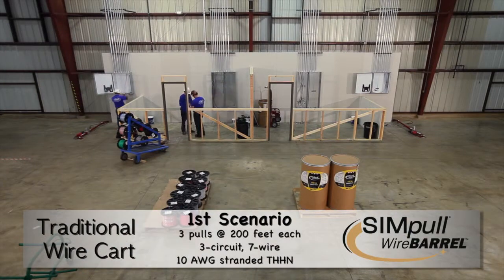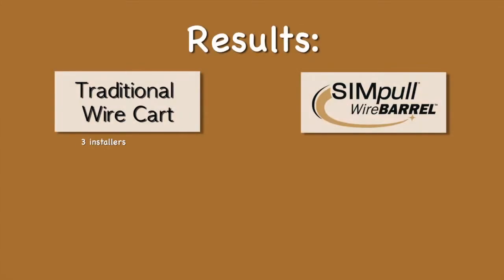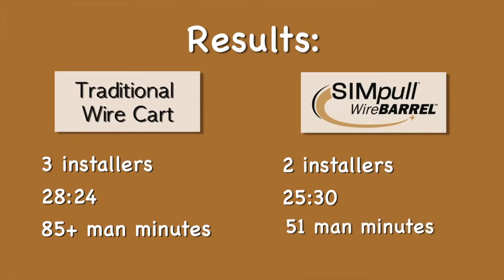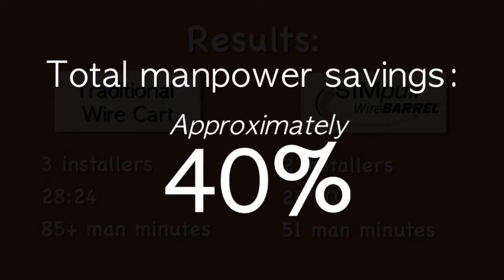Like these 30-inch doorways, allowing the wire to be located closer to the feed conduit. In this scenario, three installers using the traditional wire cart method completed their pulls in 28 minutes and 24 seconds, a total of more than 85 man minutes. The two installers using the SIMpull WireBARREL system completed their pulls in 25 minutes 30 seconds, or an equivalency of 51 total man minutes — a total manpower savings of nearly 40%.